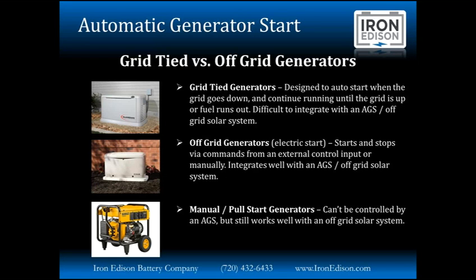They're designed to automatically start up when the grid goes down, and then continue running until one of two things happens. Either the grid comes back up, or we run out of fuel. These generators have a transfer switch included with them. So we've got our grid power coming into the transfer switch, as well as the generator power. And then the output of this transfer switch powers the entire house or whatever the loads may be. And in that transfer switch is a current sensing circuit. What it's doing is just monitoring to make sure grid power is present. So if the grid power is ever interrupted, that is going to trigger the start on this generator.